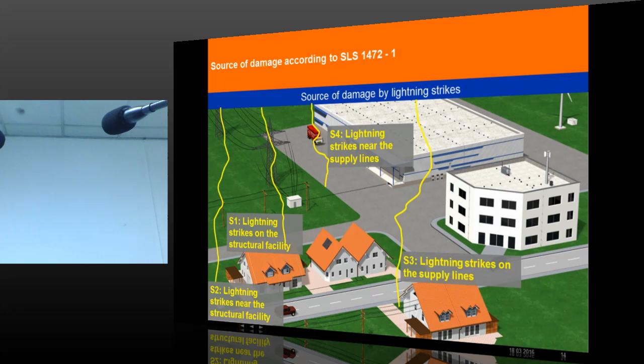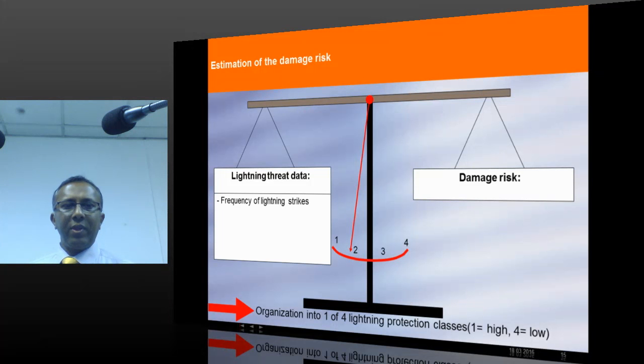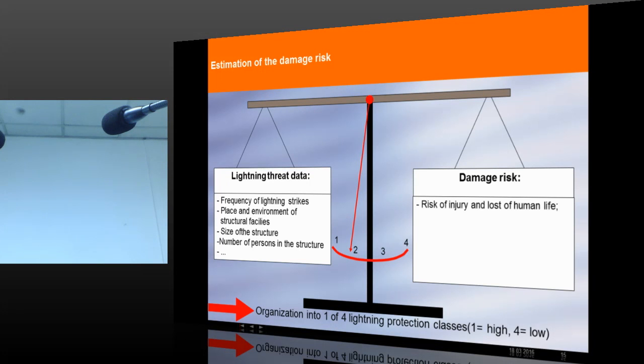And this is actually a simple way of explaining the lightning protection scenario. Imagine there is a lightning strike on a tree near your building. Whether it is S1, S2, S3 or S4, a lightning strike on a tree near your building comes under S2. So, all the four parameters are explained here, and the first point with respect to protection is estimation of the damage. In case of S1, a direct lightning strike on a building, what can happen? In case of S2, what will happen? In case of S3, what will happen? In case of S4, what will happen? So all these are evaluated with this particular chart.